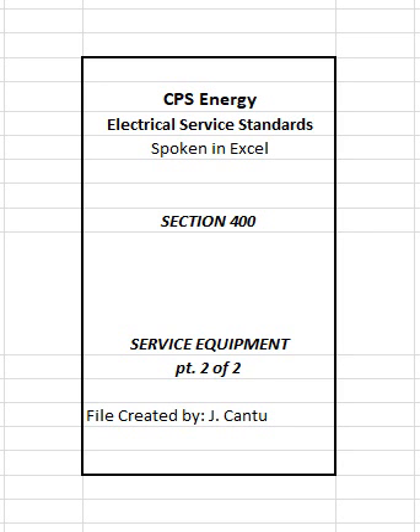410 Service raceway types permitted. Service lateral and service entrance conductors shall be installed in accordance with the NEC and other applicable codes and shall be limited to installation in the raceway type specified in the applicable respective section of these standards, refer to definition of service raceway. Note: junction boxes and/or conduit bodies are not permitted as part of raceway installations containing service conductors.